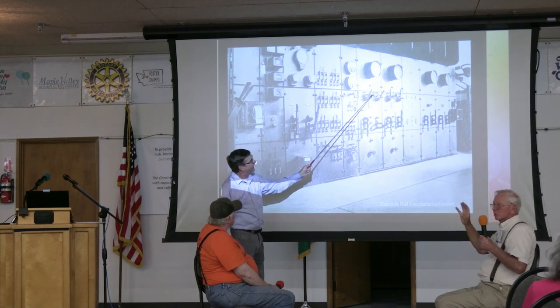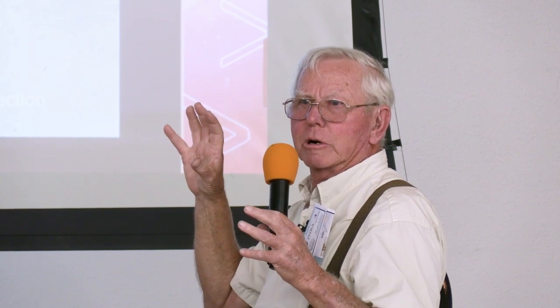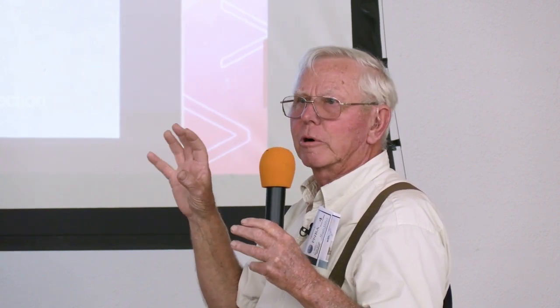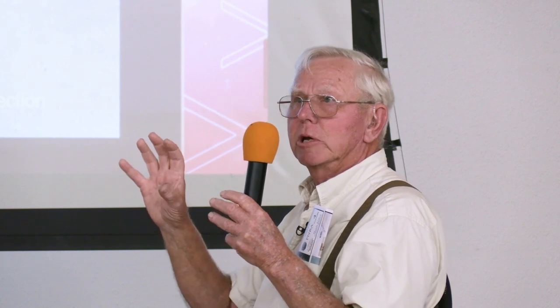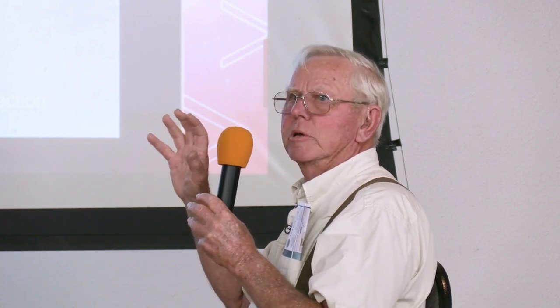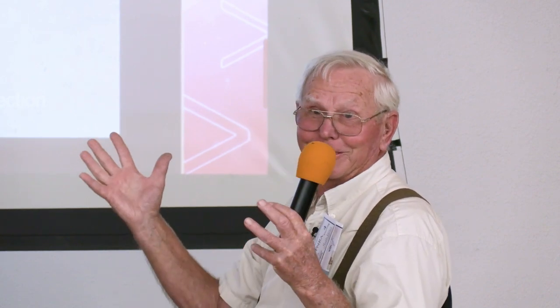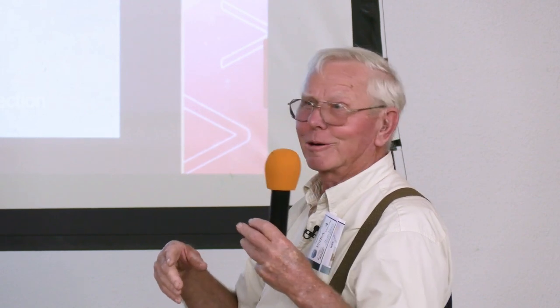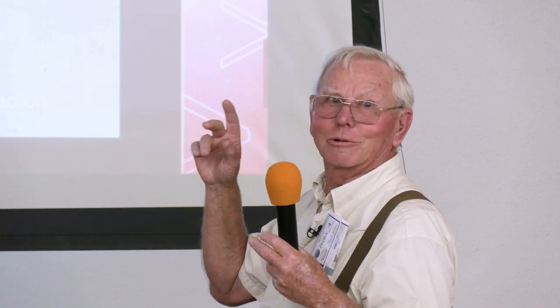So those were to balance the power on regeneration. It was very, very important, like if you had 1,000 amps coming into the substation from regeneration, you had to make sure each machine only got 500. If one machine got out of balance and got 700, it would very quickly steal everything and could overload its circuit and trip it out of the system. And then all of a sudden you got everything on the other machine, and then it tripped out too, and now you got nothing. Hopefully the train's got enough battery to run the air brakes.